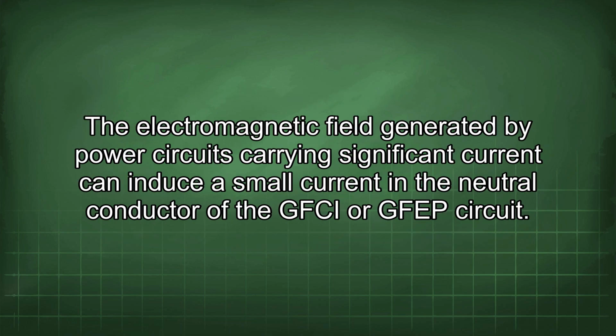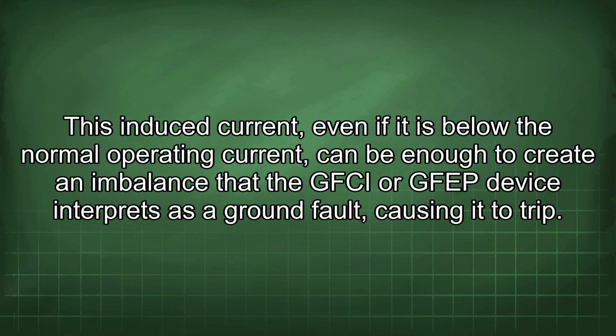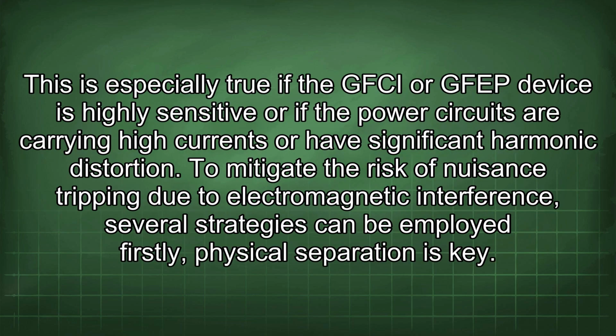The electromagnetic field generated by power circuits carrying significant current can induce a small current in the neutral conductor of the GFCI or GFEP circuit. This induced current, even if it is below the normal operating current, can be enough to create an imbalance that the GFCI or GFEP device interprets as a ground fault, causing it to trip. This is especially true if the GFCI or GFEP device is highly sensitive or if the power circuits are carrying high currents or have significant harmonic distortion.